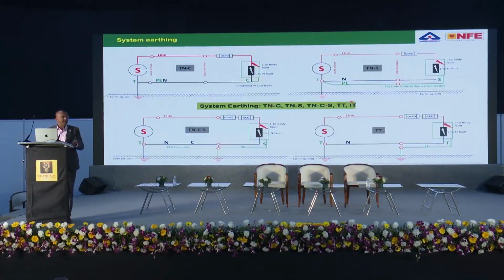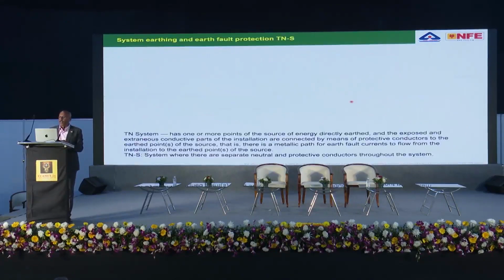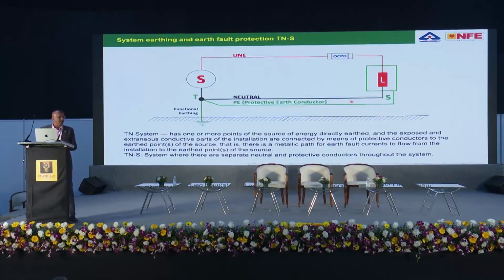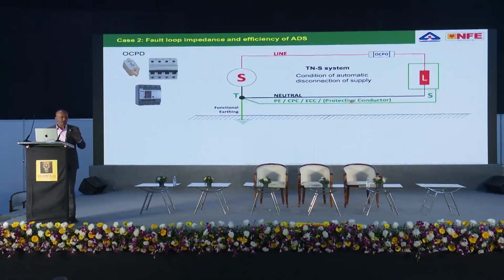Then if you want to achieve that, we go to the system earthing like TN-C, TN-S, TT, TN-C-S and all. Now I will explain what exactly I mean. For example, you have devices to trip such as MCBs, fuses, MCCBs. I am showing you a TN-S system. The definition of a TN-S system is: at the source, one of the current carrying conductors is earthed. The exposed conductive parts of the installation, meaning the metal body of the installation, are connected back to the neutral, the earthed point of the source, through a separate conductor. That means your panel board is connected back to the neutral through a separate conductor.